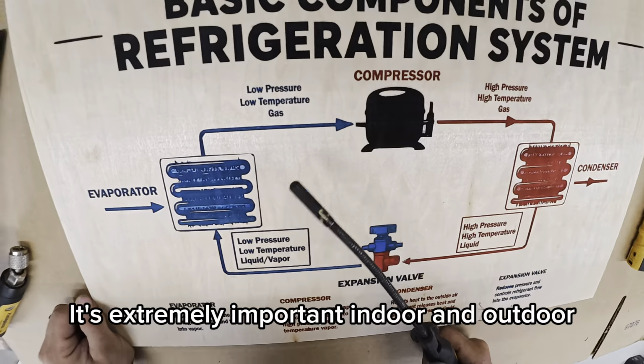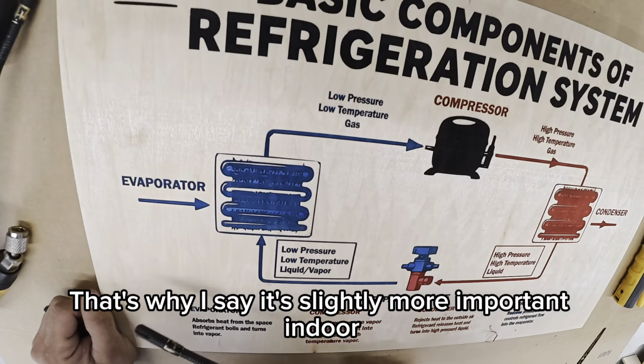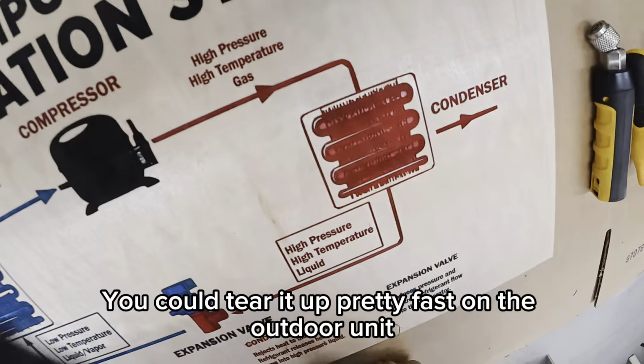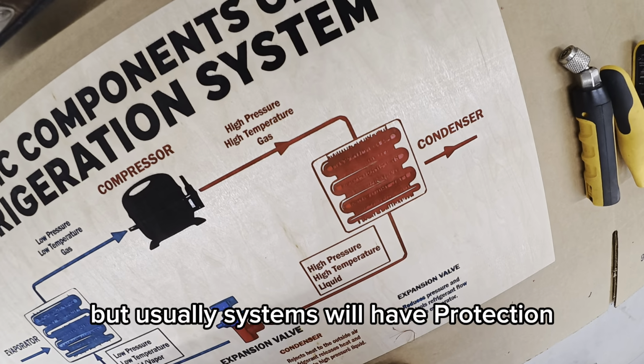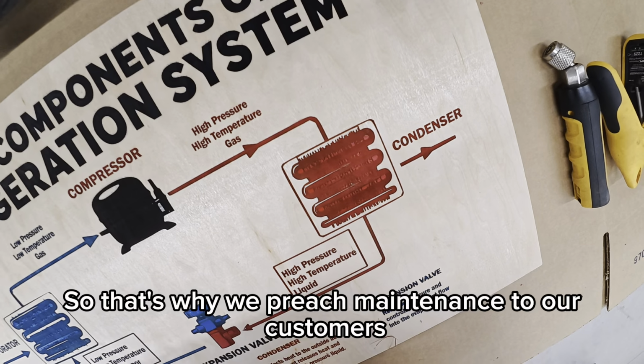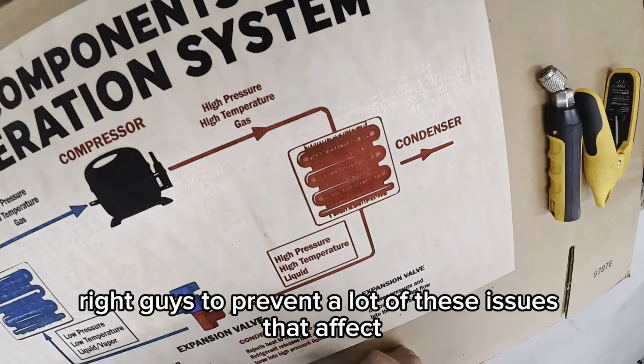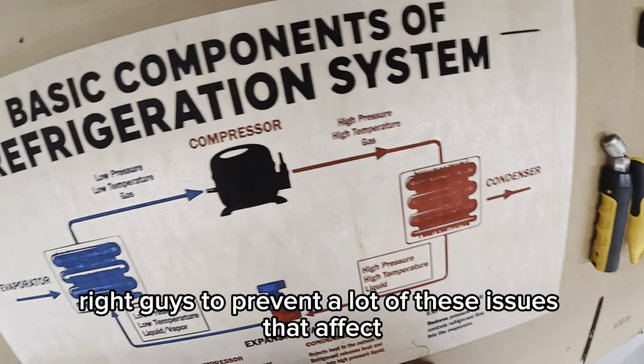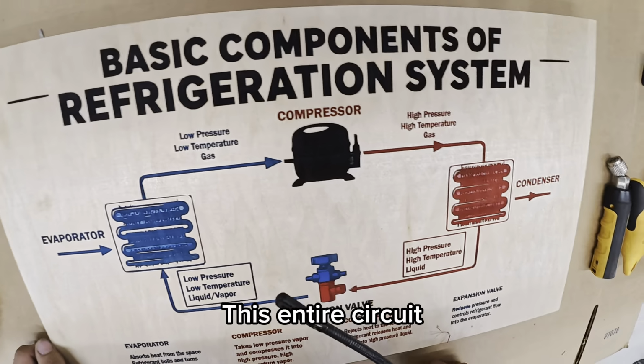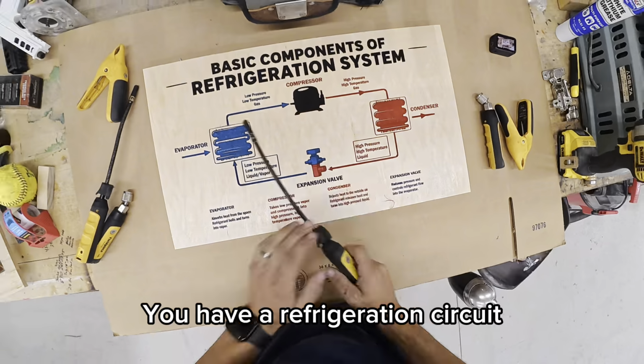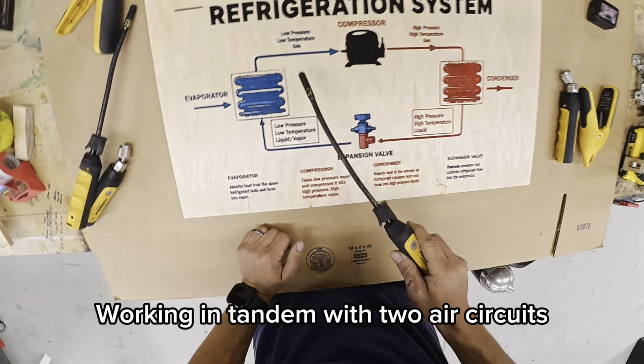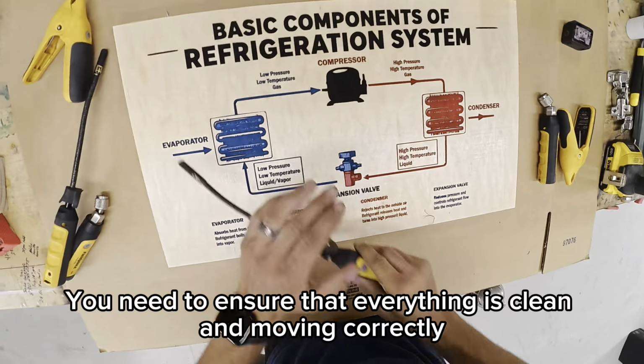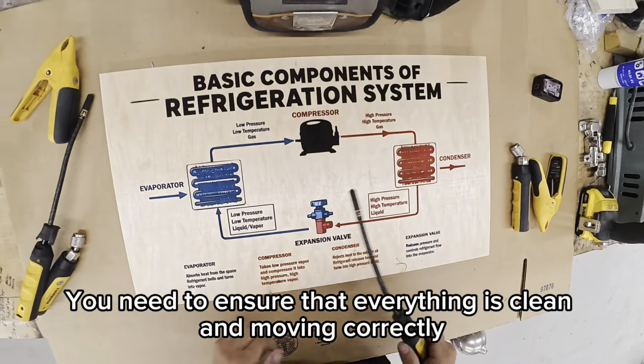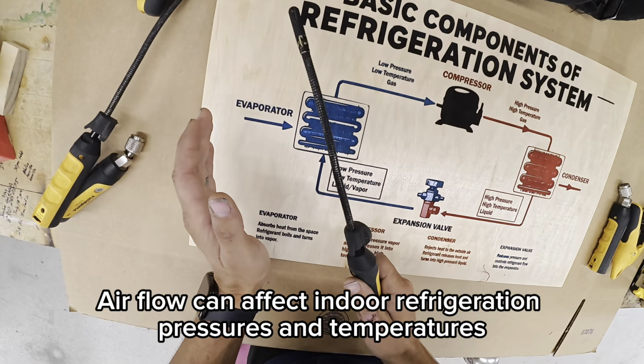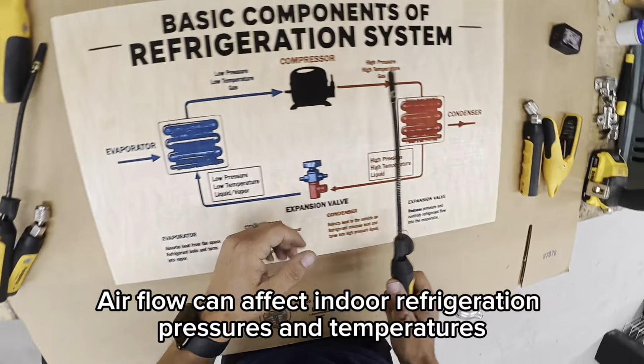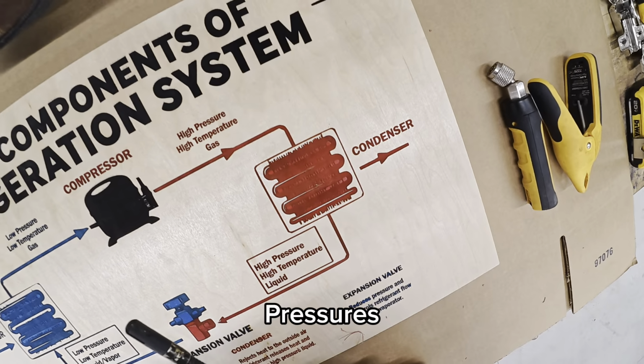Airflow is extremely important, indoor and outdoor. That's why I say it's slightly more important indoor. Really tear the compressor up. You could tear it up pretty fast on the outdoor unit, but usually systems will have protection to prevent that. So that's why we preach maintenance to our customers, right, guys? To prevent a lot of these issues that affect this refrigeration cycle, this entire circuit. So always remember, guys, you have a refrigeration circuit working in tandem with 2 air circuits. You need to ensure that everything is clean and moving correctly. And you need to understand that, hey, airflow can affect indoor refrigeration pressures and temperatures. Airflow can affect outdoor temperatures, pressures, and things like that.